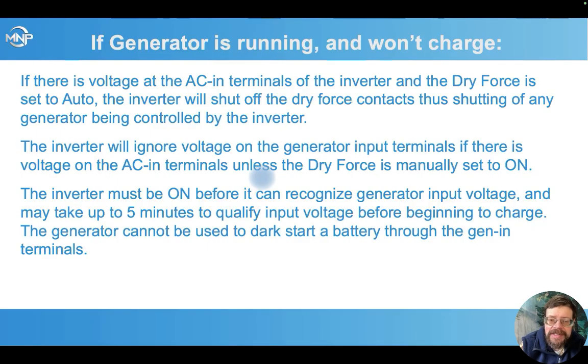Is there voltage on the AC in terminals of the inverter? If there is, it'll default to using that instead of the generator input. And also give it time to recognize the generator input voltage and to qualify that input voltage and make sure it's all within the proper ranges before it begins to charge. And remember that it can't be used to dark start a battery through the generator input terminals. The inverter has to already be on, its brain on, and be able to watch that generator voltage and then close that relay to start using it.